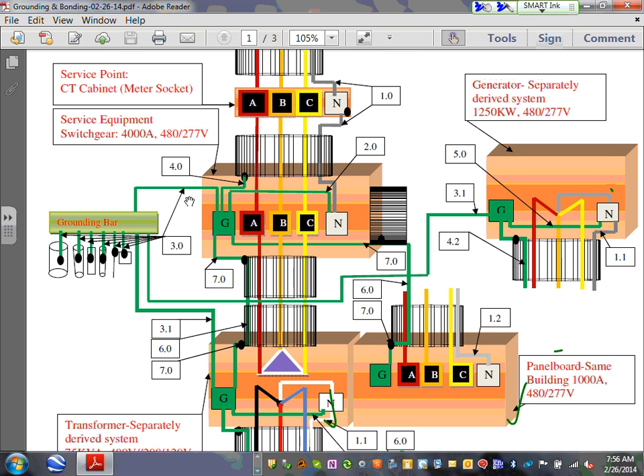So Derek, my friend, 3.0, can you guys see it right here? 3.0 is called the grounding electrode conductor. The grounding electrode conductor is the conductor that you take from the ground bar in the switchgear directly to the ground rod, concrete encased electrodes, anything metallic in direct contact with Mother Earth. That's called the grounding electrode conductor, right in here. Do you guys remember when we went to Boston Scientific? You saw that copper bar, right, in the electrical room, attached to the wall, and there are all these grounding conductors attached to it. That's what you see right here.